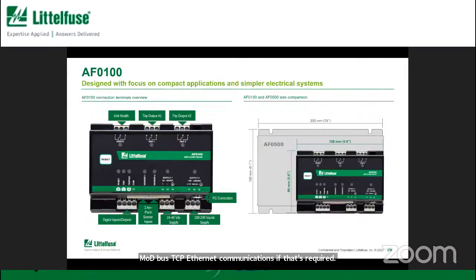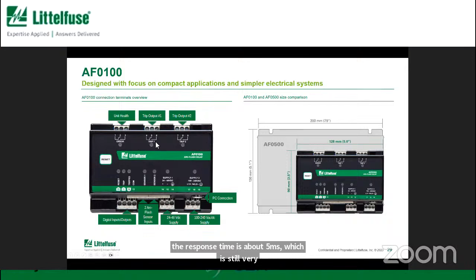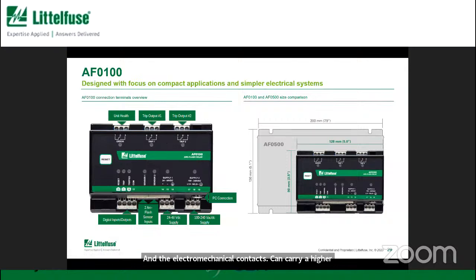Now, if you have a little smaller panel where you do not require very many light sensors, maybe you only need 1 or 2 sensors, the AF0100 is a great option. So it's a smaller package and it uses the same sensors, has the same redundant circuit inside. It's just a smaller package for the 2 sensors. And this model, these outputs are electromechanical. So the response time is about 5 milliseconds, which is still very quick. And the electromechanical contacts can carry a higher continuous current. So it depends on the type of circuit breaker you are trying to trip.